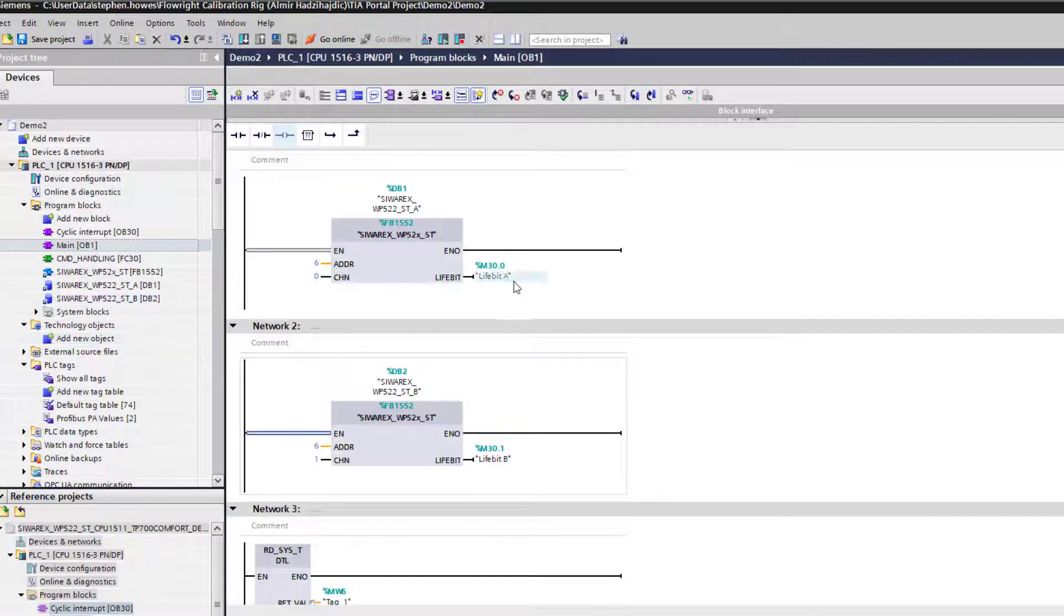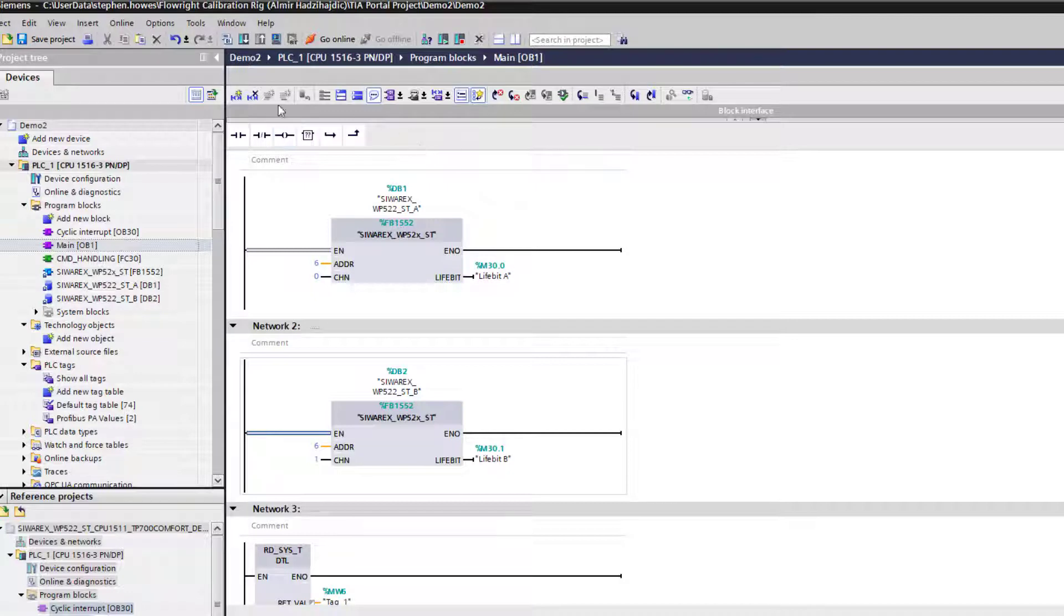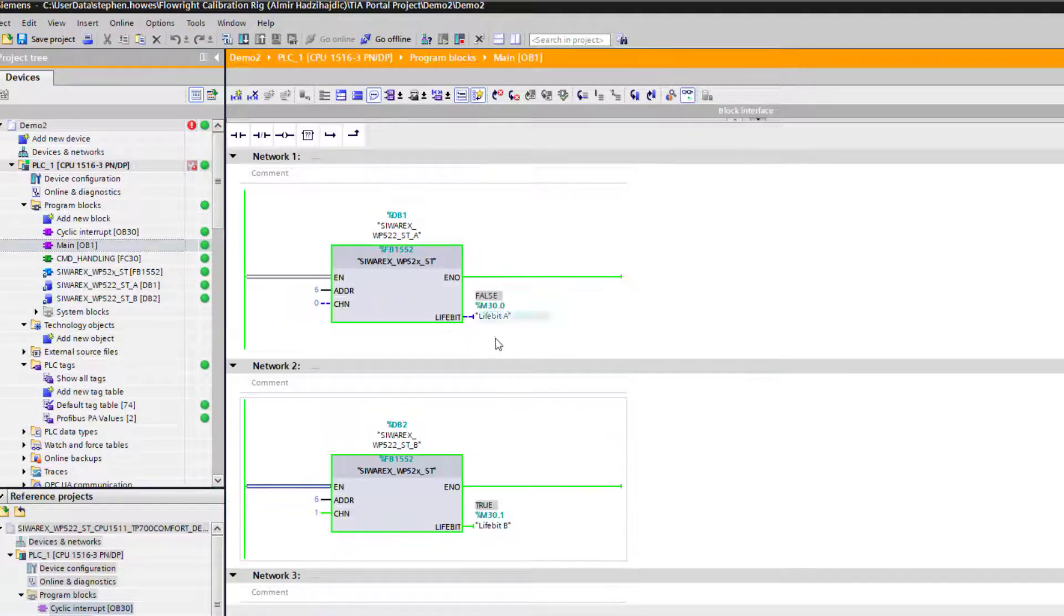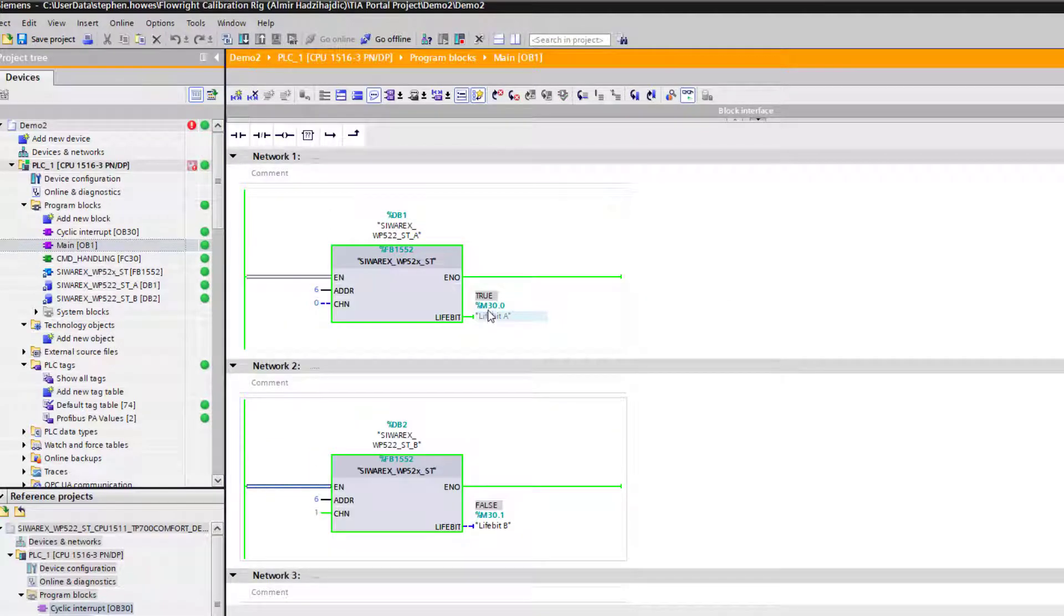What we're trying to see now to prove that this block is working, if we go online, what we want to see is this life bit toggling. That's the key to the SIWAREX. As soon as you see these life bits toggling, the likelihood is that the block is working.